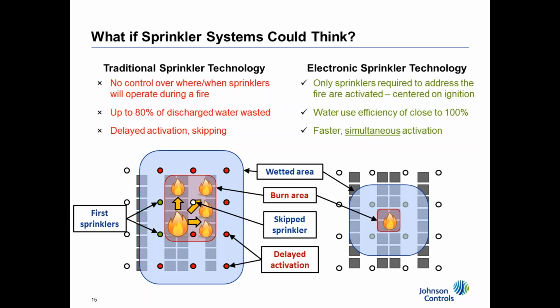So what if your sprinklers could really think, as opposed to letting just the heat itself decide? When you look at traditional sprinklers, there's no control over when and where sprinklers are going to operate. About 80% of your water discharge is what we would call wasted water, meaning the water may be discharged from sprinklers outside of the area of actual fire. In delayed activations, you also have a phenomenon called skipping of sprinklers. You may have a fire dead center of the fire plume that never actuates because of the way the heat transfer is at that ceiling. It may come up and bank before it ever really gets to the thermal sensing element. With electronic sprinklers, we can actually tell which sprinklers to activate, which allows us to use 100% water efficiency, as opposed to a situation where you may have sprinklers outside of your fire ring actuating.